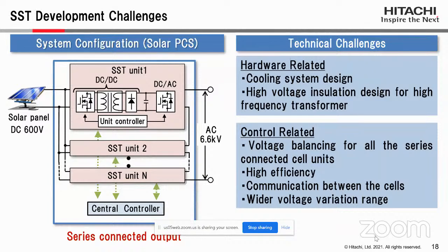The second hardware related issue is the high voltage insulation design for the high frequency transformer. As it is connected to a 6.6 kV system, and at the input side we have a low voltage DC, we need a very high isolation between the primary and secondary side. So suppose for a 6.6 kV application, we need insulation of 30 kV. To achieve that insulation voltage, there are challenges in the transformer design to optimize the transformer size and at the same time to have a high efficiency.